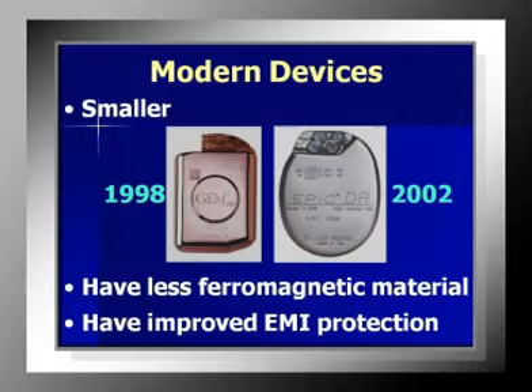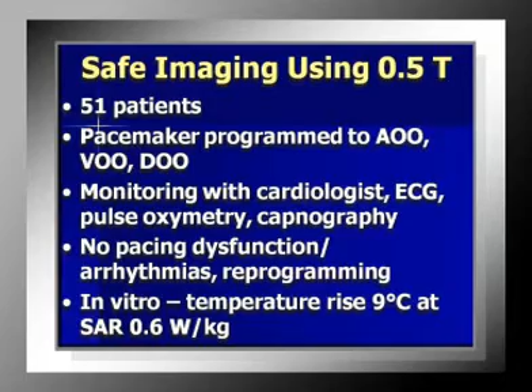So these are older devices, and newer devices. They have less ferromagnetic material. They're smaller and have improved electromagnetic interference protection. At 0.5 Tesla, 51 patients had no problems. At 1.5 Tesla, there were 107 leads and 61 pacemaker generators. A number of studies were done. No adverse events occurred, and no studies were interrupted. But there were a number of lead changes, and these were in older devices.